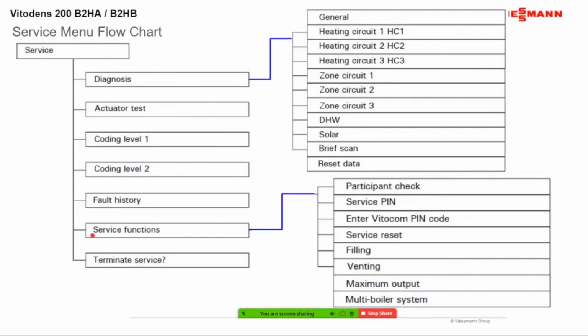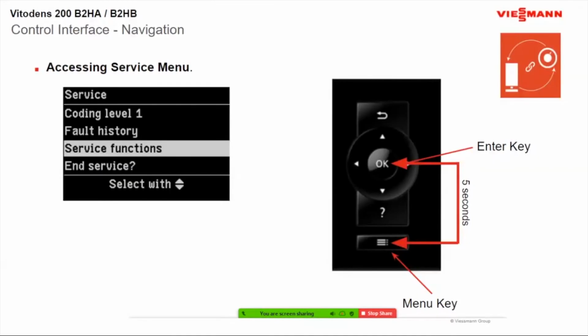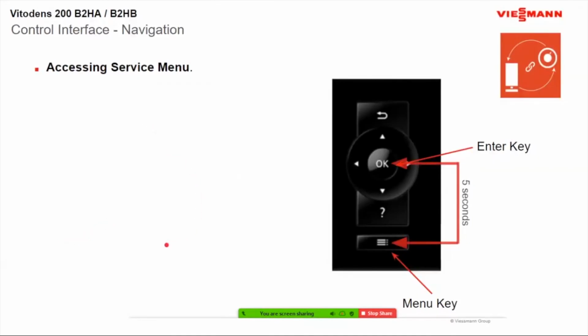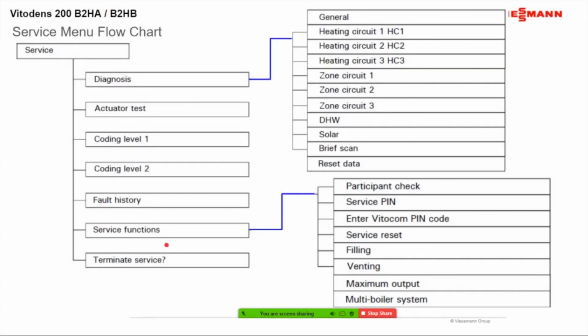So when we push these buttons, we hit the service button, so service menu here, service functions, service menu. We can now see the different things that we can see here. If we go into diagnosis, diagnosis is a good, helpful tool. You can see all your actuals, your set points, your outdoor temperature, actual and dampened. Is my pump on? Things like that. So it's a good way to see how everything's working. The actuator test is a really neat thing as well. This is where you would do your high and low fire test, through actuator test. I'll have a sub menu come up here shortly.